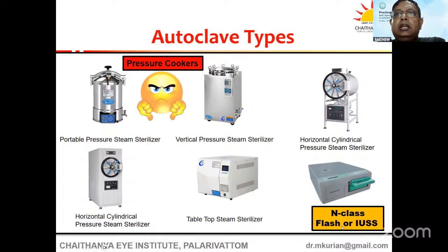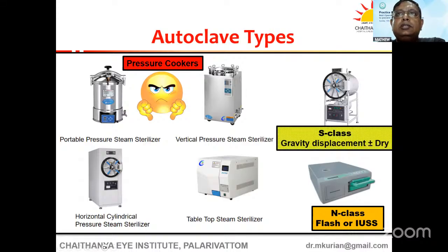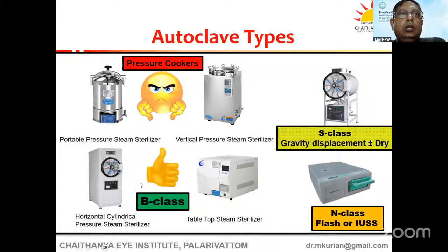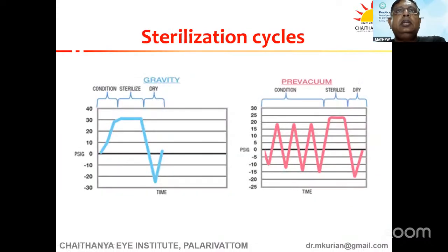The flash or N-class autoclaves are for immediate use steam sterilization, but this is not a routine recommendation for clinical use. It can be used in a situation where a critical instrument becomes unexpectedly unsterile during the procedure and you need to recover it. Horizontal steam sterilizers are gravity displacement, but with a dry cycle can be used safely. But what is recommended is a Class B sterilizer. Class B is typically used for tabletop sterilizers, but horizontal, rectangular or cylindrical high pressure steam sterilizers also meet. They are not called Class B, but they have a separate ISO number. Okay, but equivalent to Class B.